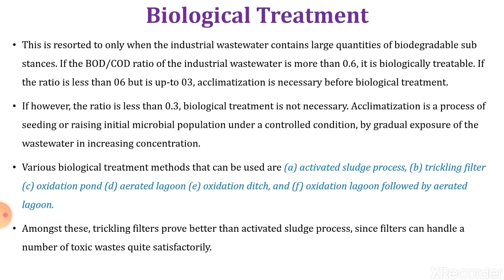If the BOD/COD ratio is less than 0.6 but up to 0.3, acclimatization is necessary before biological treatment. If the COD is greater, this ratio will go below 0.6 or even to 0.3, and acclimatization is required. If the ratio is less than 0.3, biological treatment is not recommended. Acclimalization is the process of seeding or raising the initial microbial population under controlled conditions by gradual exposure to the wastewater in increasing concentration.